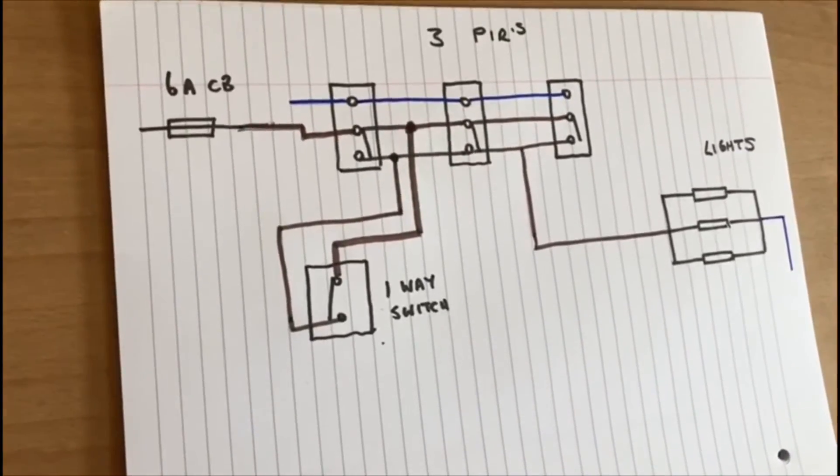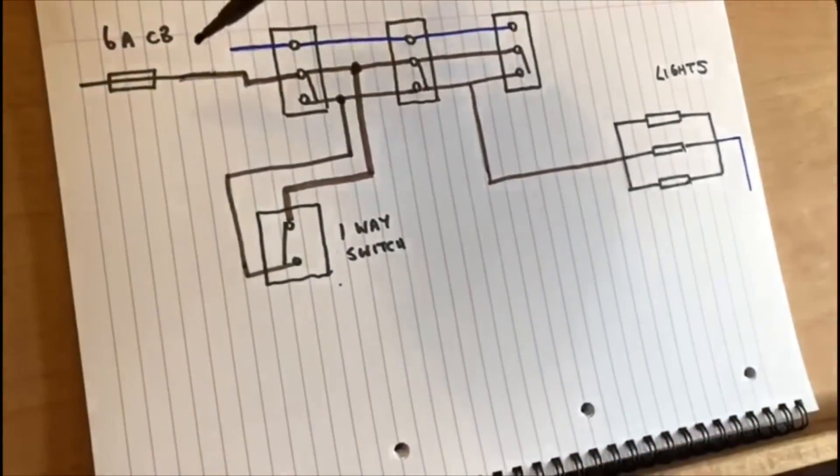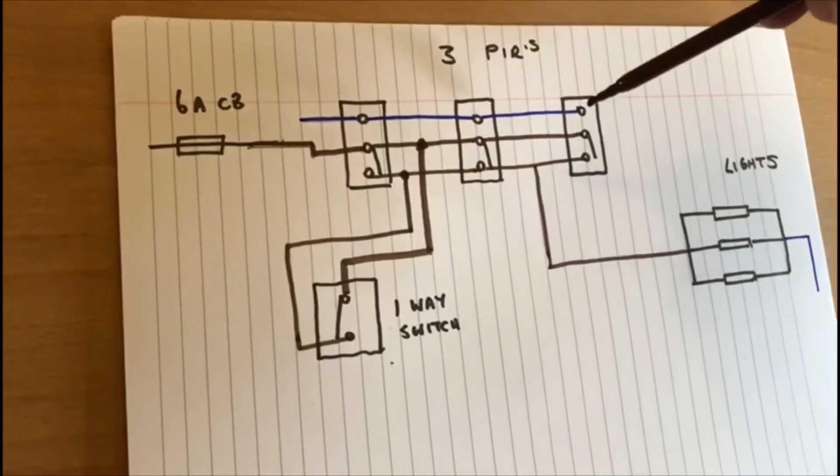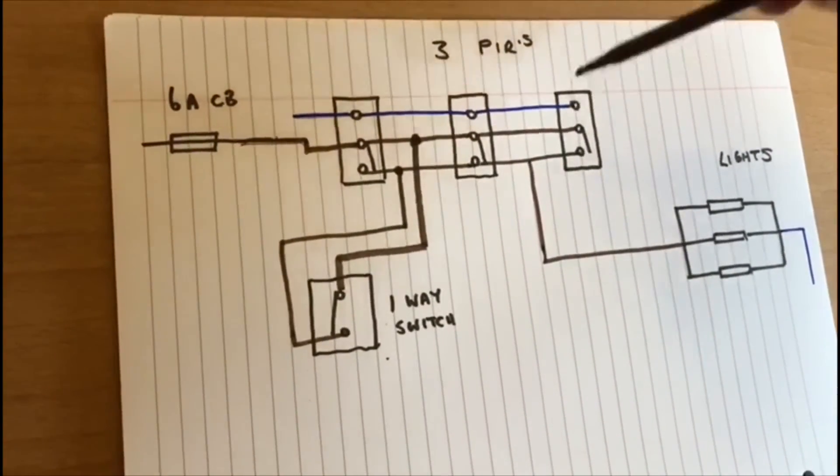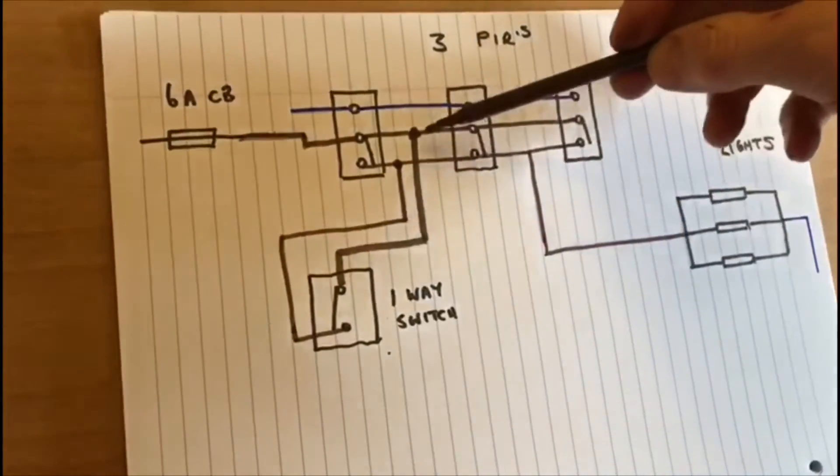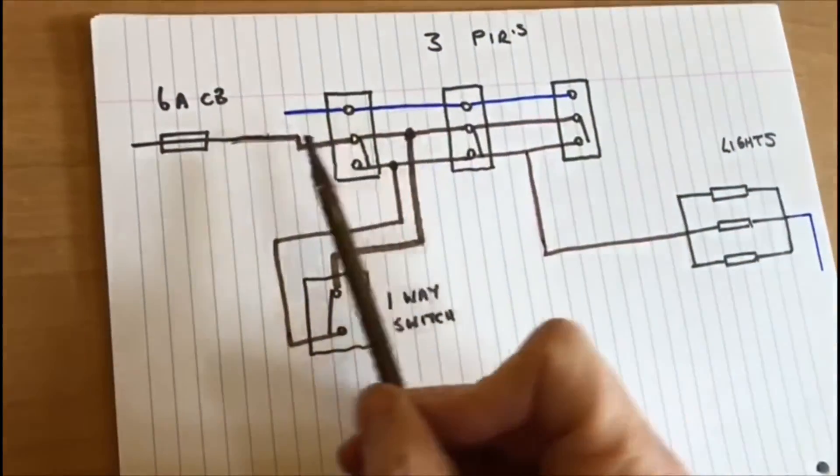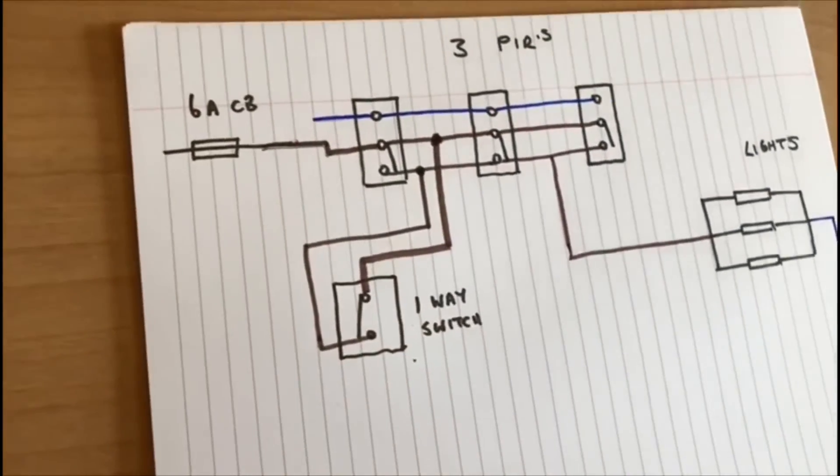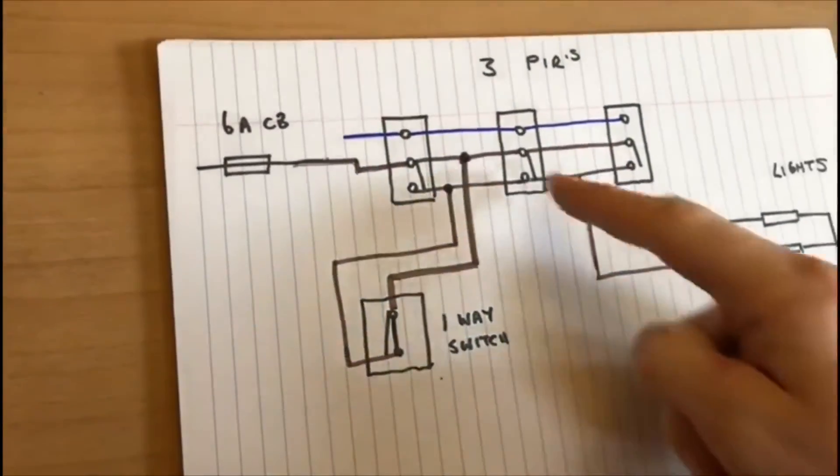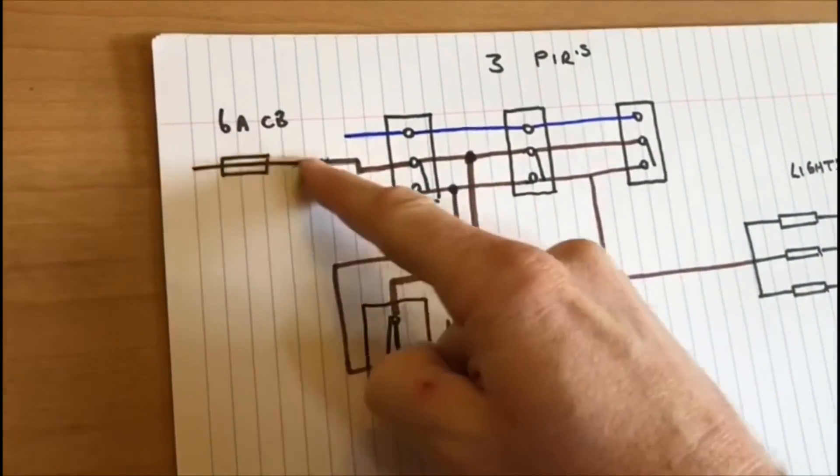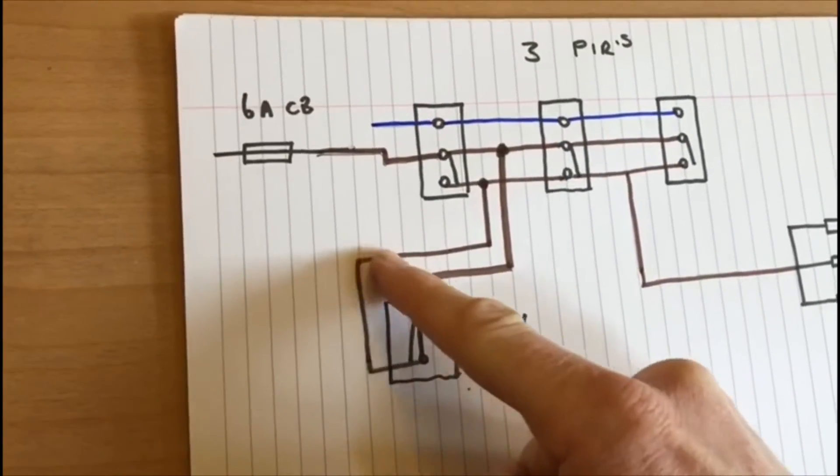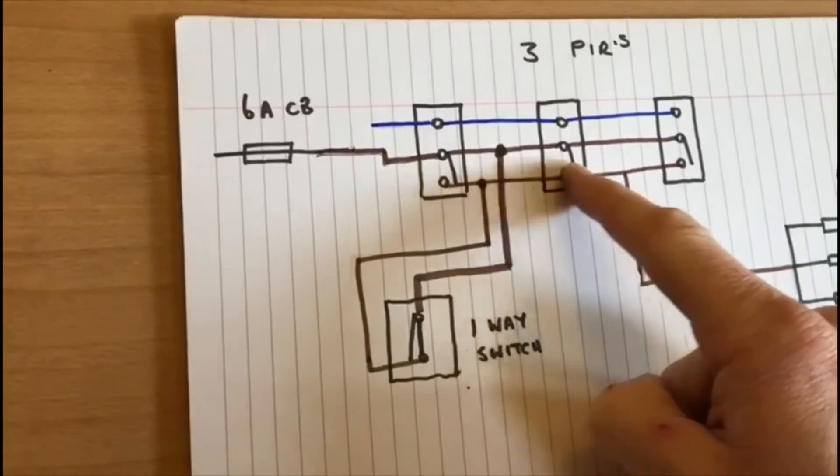We've still got the permanent live running into all three PIRs, so at no point does the permanent live get disconnected. All three PIRs are permanently live. But this time we have a one-way switch. It's still in parallel with these switches, so if this switch was to be closed, now you've got a circuit running through here, down through here, down through the switch, back up.